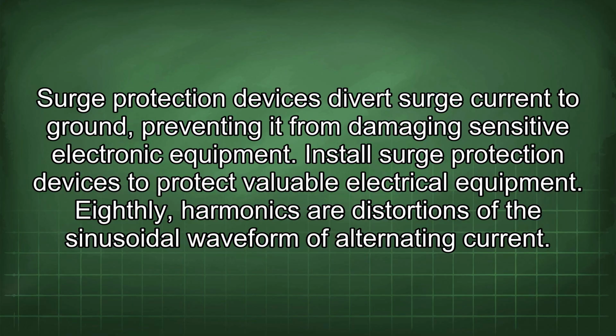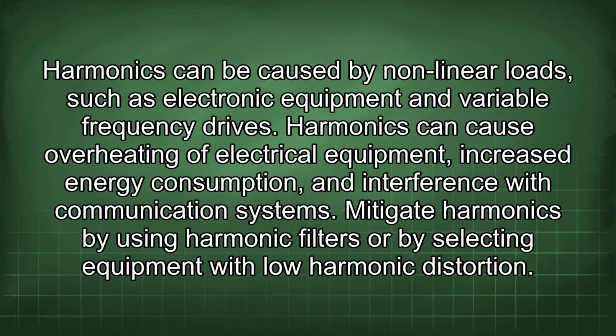Eighthly, harmonics are distortions of the sinusoidal waveform of alternating current. Harmonics can be caused by nonlinear loads such as electronic equipment and variable frequency drives. Harmonics can cause overheating of electrical equipment, increased energy consumption, and interference with communication systems. Mitigate harmonics by using harmonic filters or by selecting equipment with low harmonic distortion.